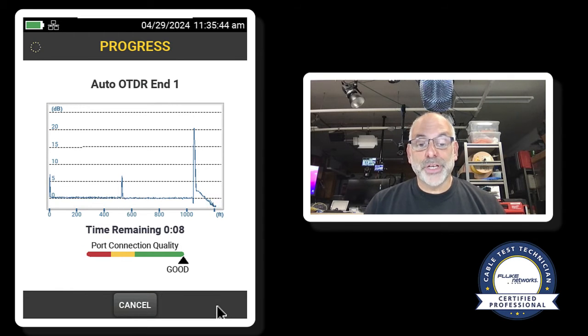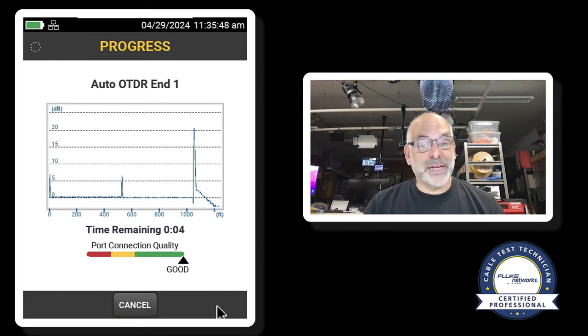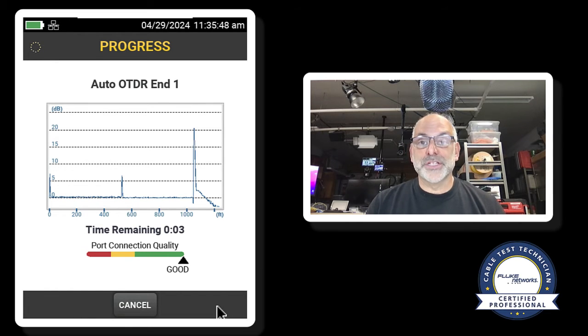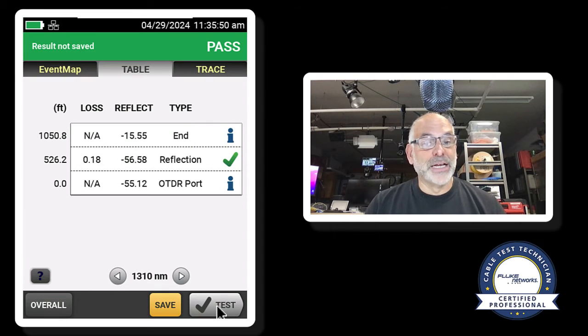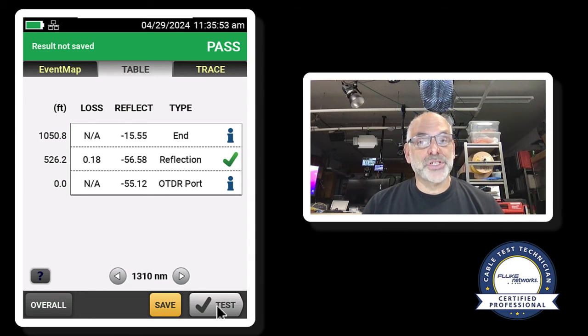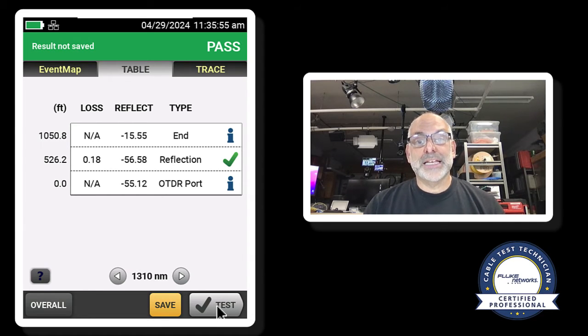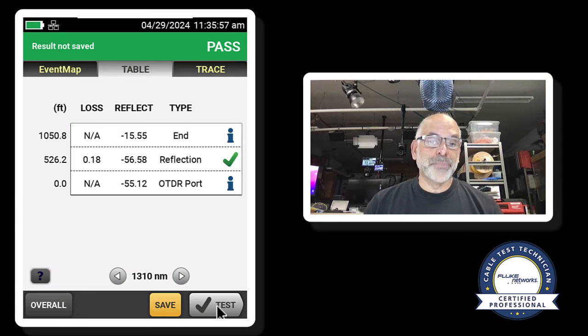If this is not green when we run this test, stop what you're doing, inspect that port, inspect the fiber. Because if that is not green, there is no sense going on. Any testing we do will be invalid.